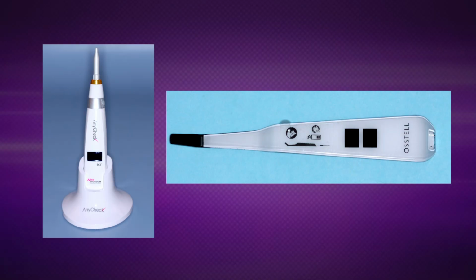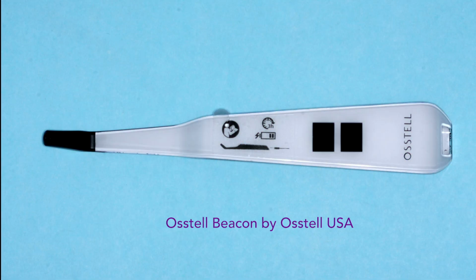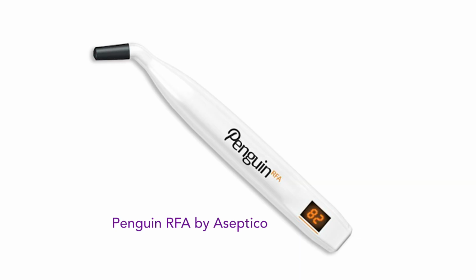There are 2 technologies that are prevalent with implant stability testers, but they work on the same principle. All structures that are rigid vibrate with a high frequency, and that's the simple principle that both of these technologies use. One puts a special peg on the implant, and that peg has a small magnet in it, and it's activated with magnetic pulses, and the resonant frequency is analyzed. These are called resonant frequency analysis devices, such as the Osstell units or the Penguin RFA unit. These are very accurate, and they're well proven in studies.